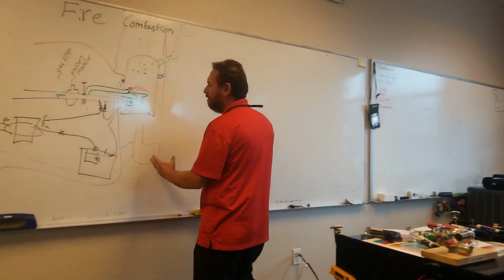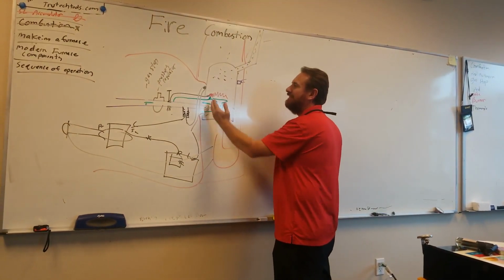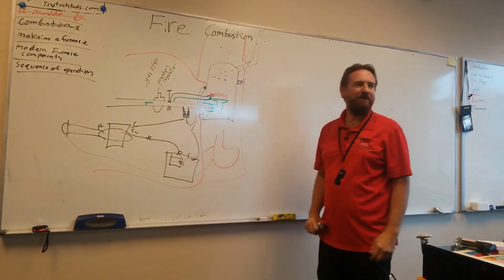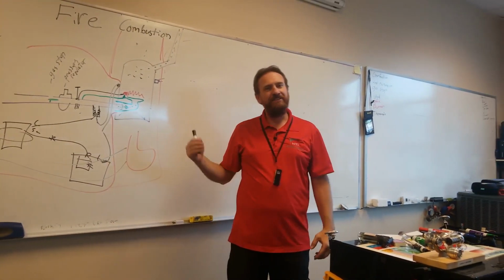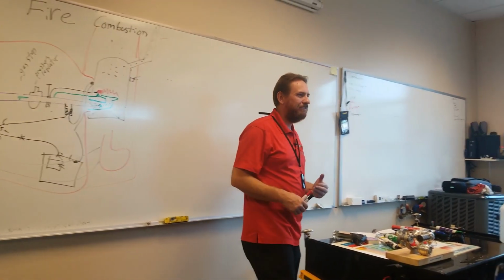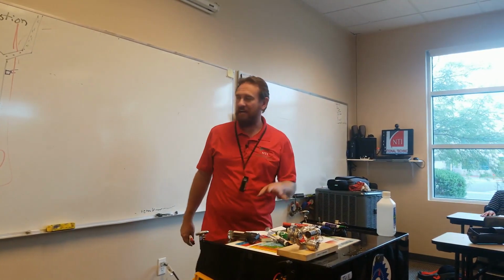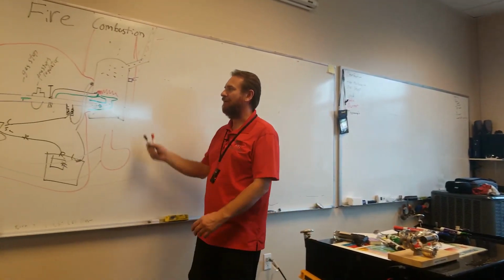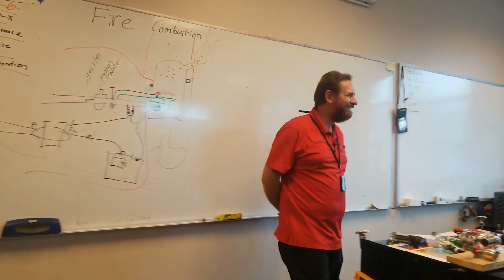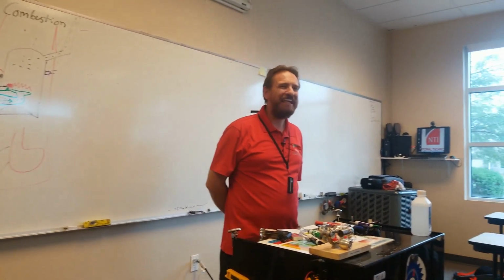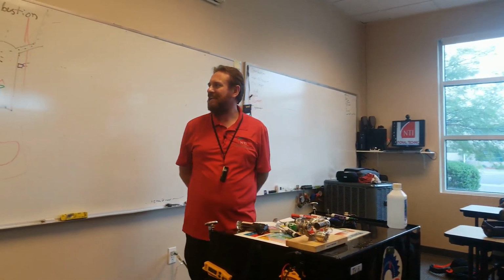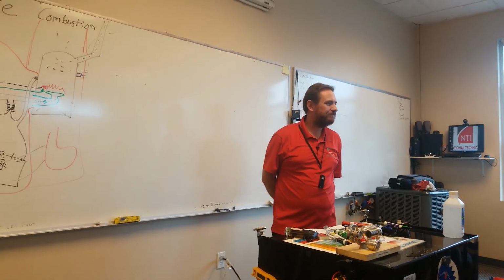So now I'm blowing air on the outside of that heat exchanger. Where's the fire burning? Inside. Does the fire and the air ever mix? No, it's completely separate. The air we're burning is separate from the air going around it. Pretty neat, huh? Now we have a gas furnace. We have now made a basic gas furnace.